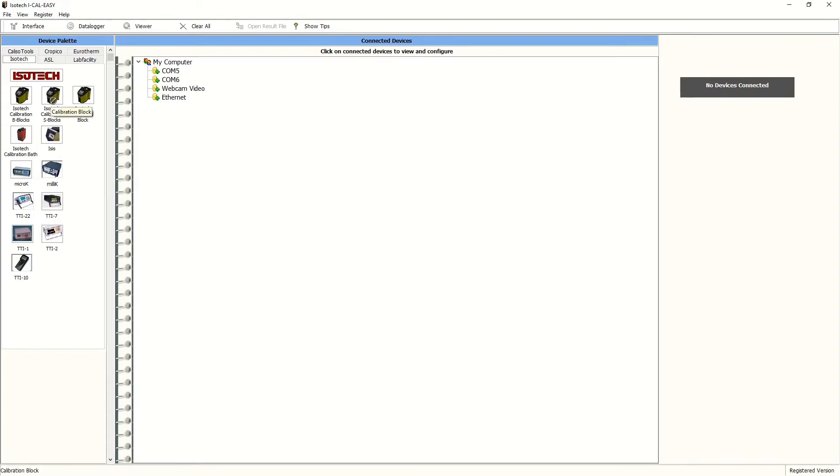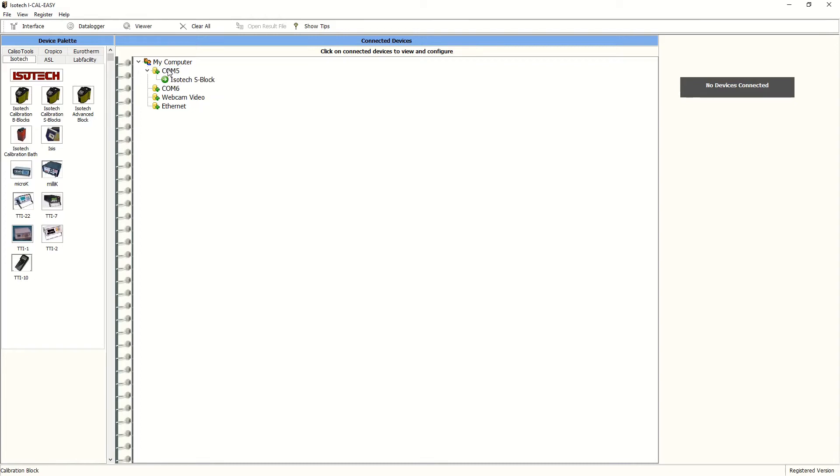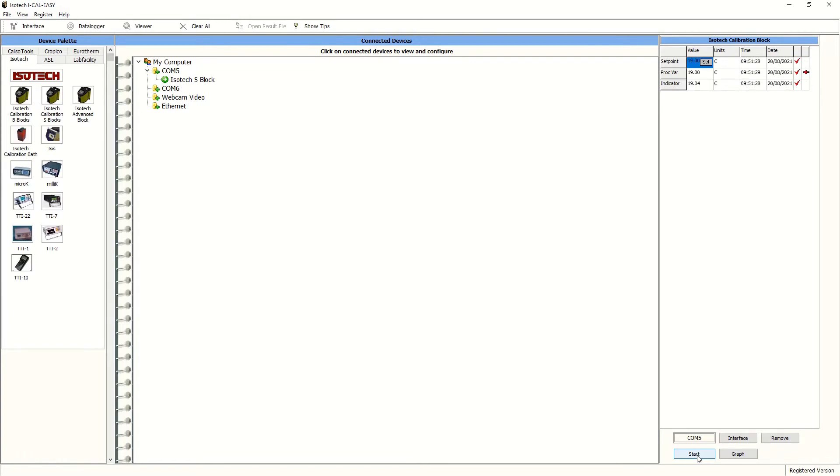We select the dry block that we're using - we're using a S-Block model dry block from Isotech and drag and drop this onto the COM port which is connected to the converter. We then press start and this should then open the port and bring the signal in from the dry block. And there we are.